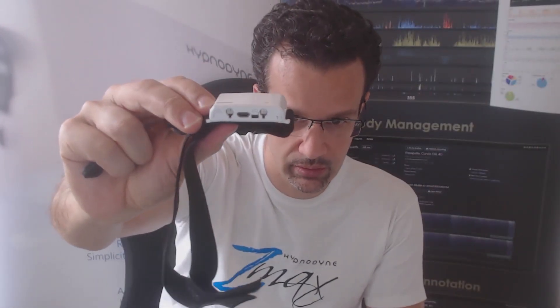The sensor looks like this. You can see that it's very, very small, particularly the connector. The reason for the connector being that small is that ZMAX itself is extremely small, so the port into which you plug the connector also needs to be really, really small. It was so difficult to make a port this small that I went ahead and filed a patent on it, because it's not something that you can buy on the market. By contrast, you look at the USB connector, it seems huge. The SpO2 connector is that black rectangle just next to the USB port — on the video I think it's going to show up on the right side.